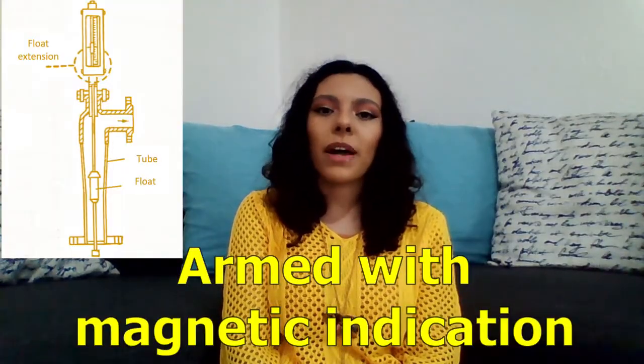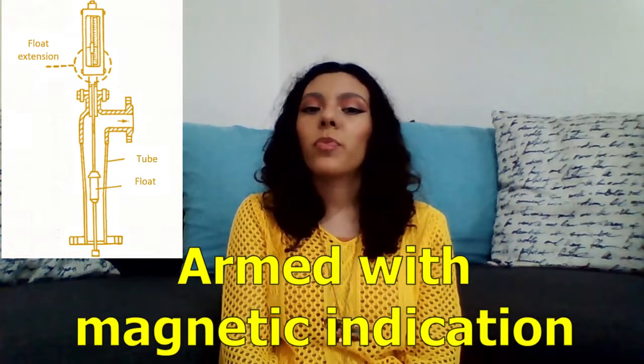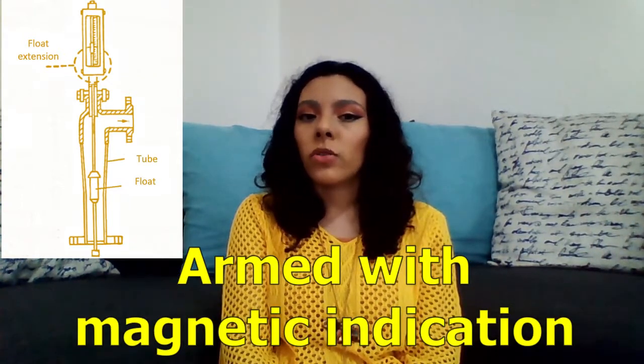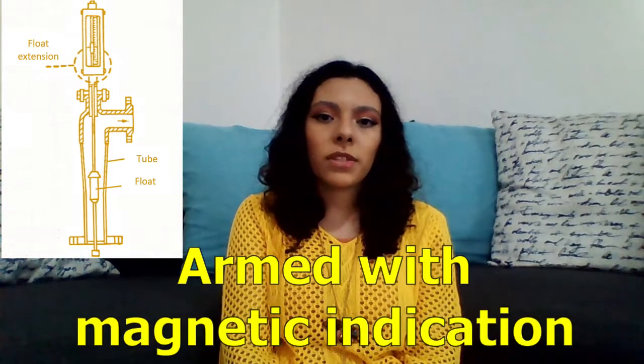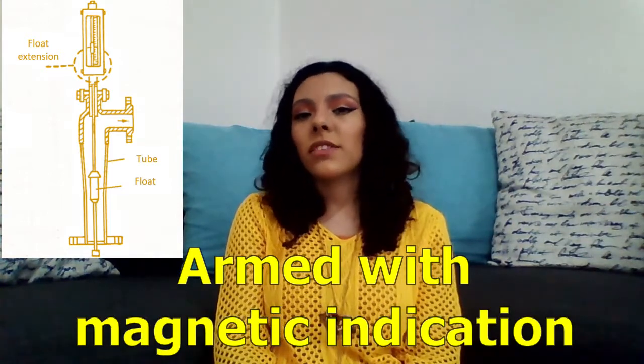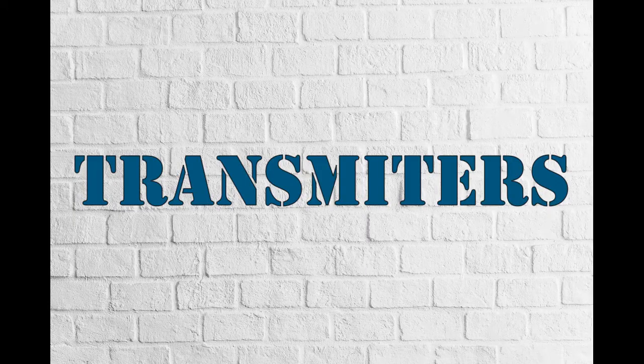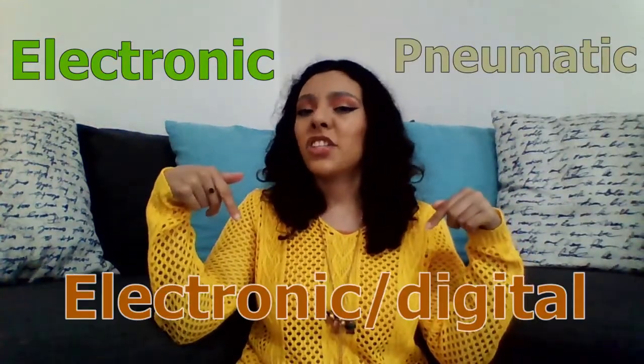Rotameters armed with magnetic indication. These incorporate a metal tube that does not allow the direct reading of the flow to be seen, so they need indication and transmission. There are pneumatic, electronic, and electronic digital transmitters.